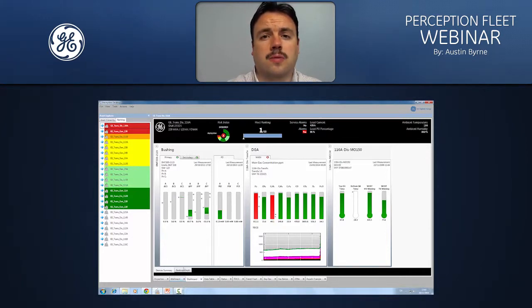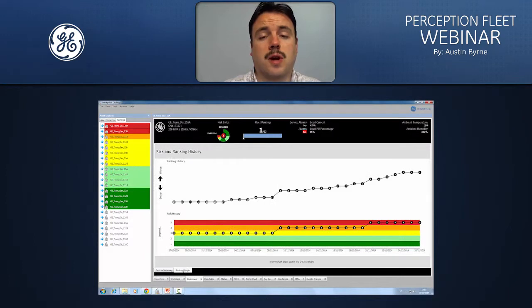Our other unique transformer dashboard is our ranking graph history dashboard, which shows you the history of the asset over time in terms of its risk evaluation and its ranking. So where the top circle risk index showed you a 9-month snapshot of the asset's journey, the risk index chart shows you a 30-day evaluation, and it also gives you more detail. So you can see 30 days ago this asset was in risk index of yellow, and now it's in risk index of red, risk index 5.